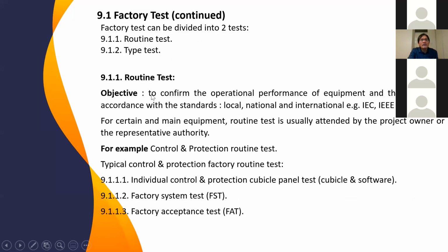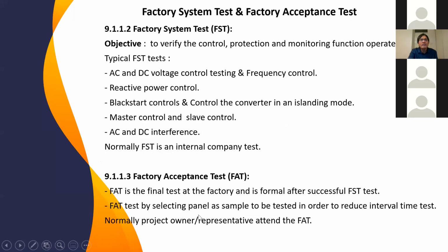Routine tests, the objective is to confirm operational performance of equipment. For certain main equipment, routine tests actually will be attended by the project owner. What is the main equipment? For example, control and protection routine tests. There are 3 types of tests for control: individual control and protection, where we test cubicle and software individually. And then the next step will be FST, and then the last one, FAT.